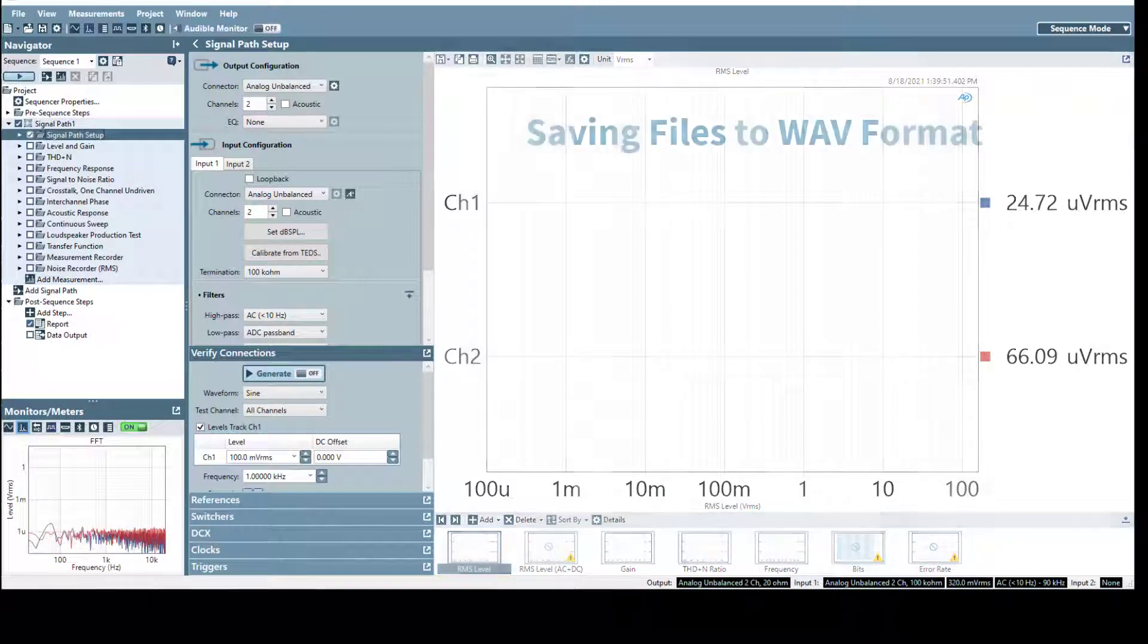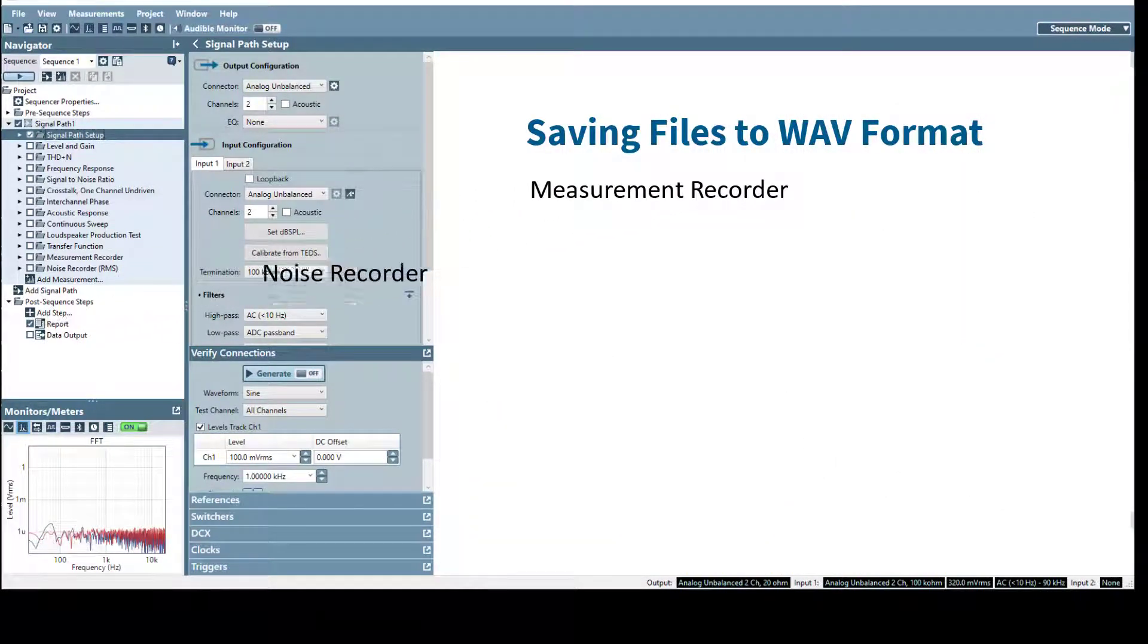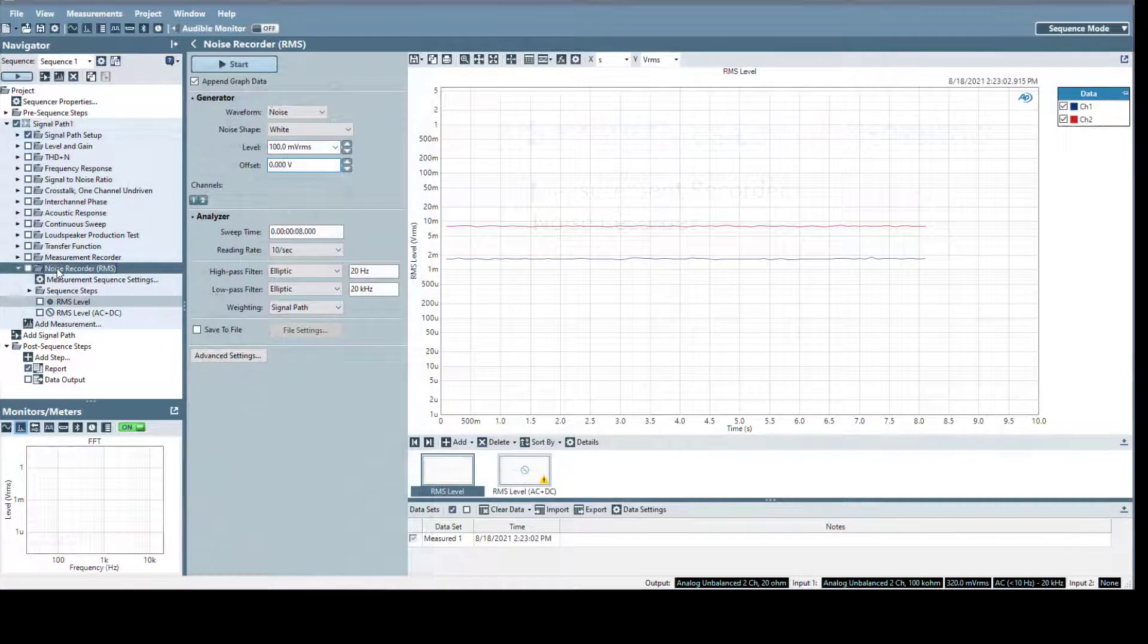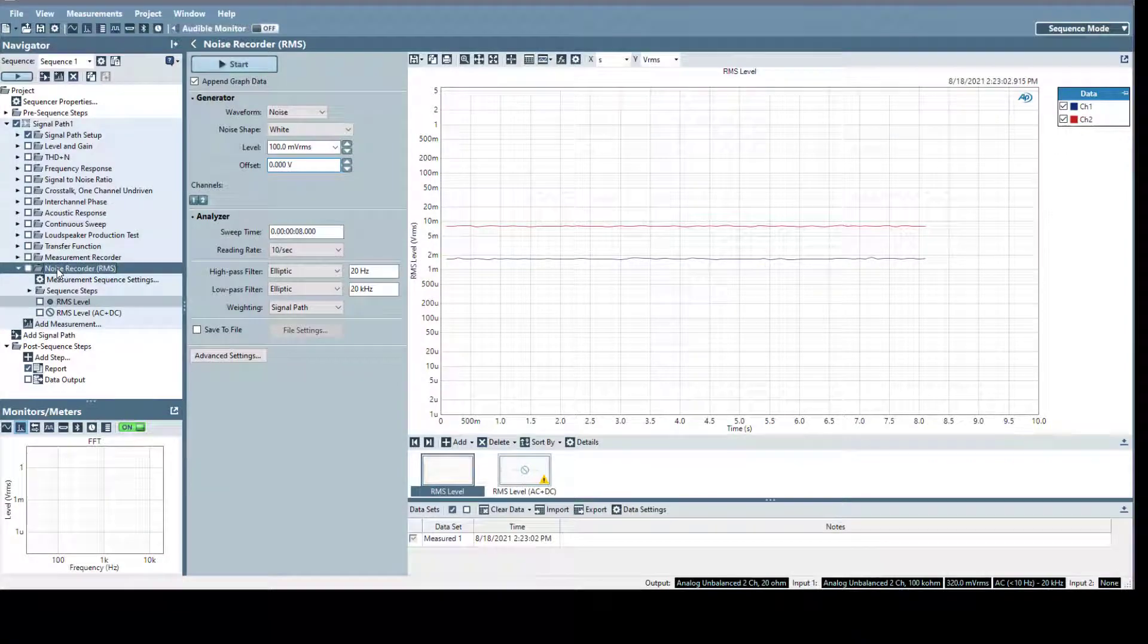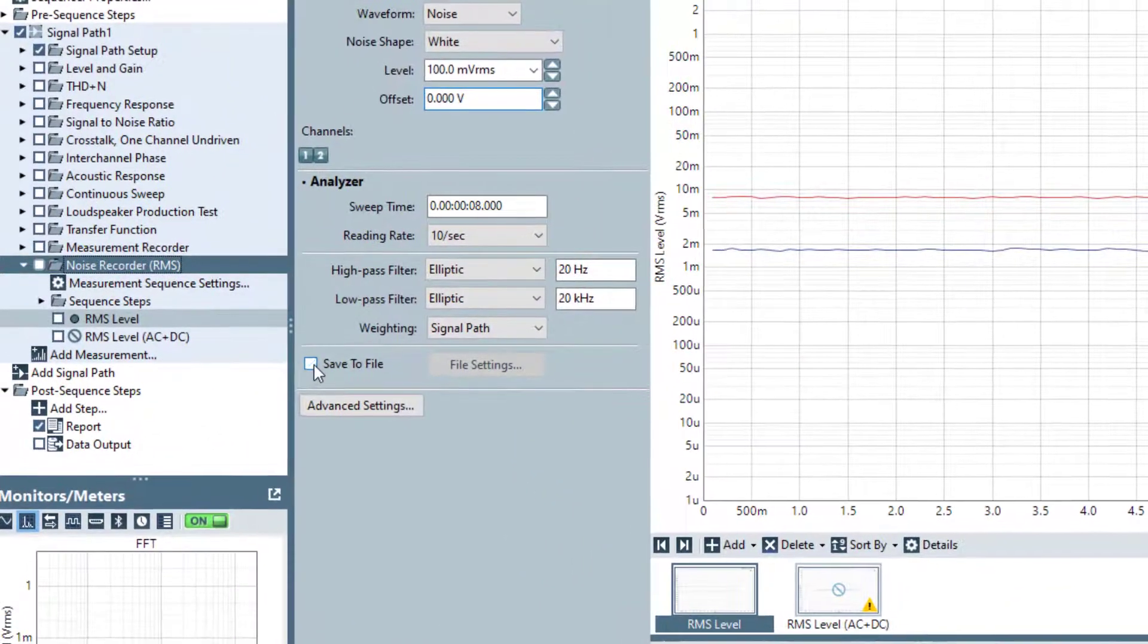Until APX500 v6.1, only measurement recorder and noise recorder measurements have had the option to save result data to WAV files, but this feature requires turning on the WAV capture in advance of making acquisitions.